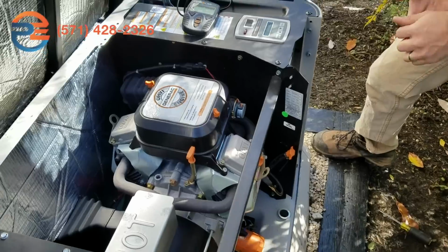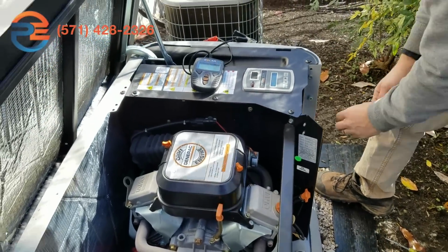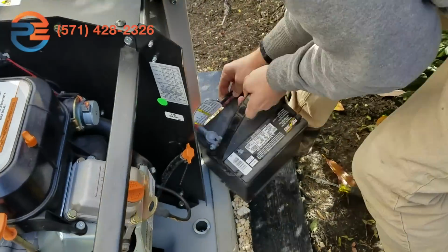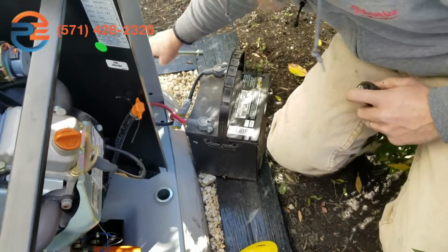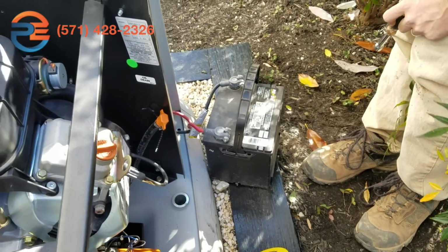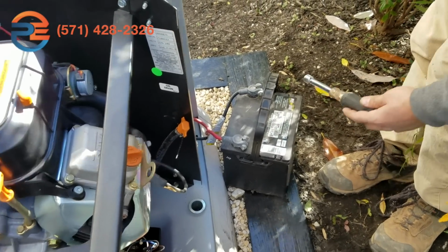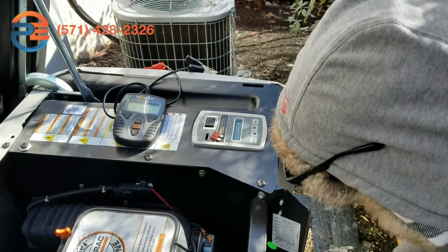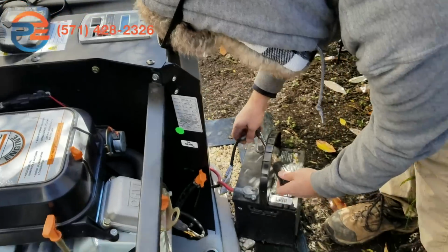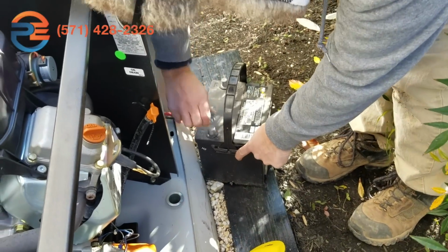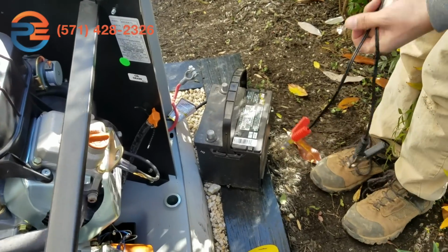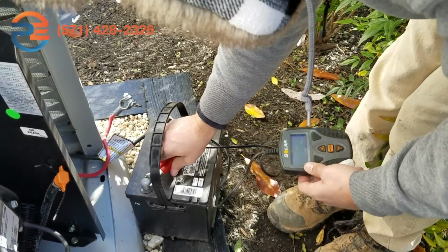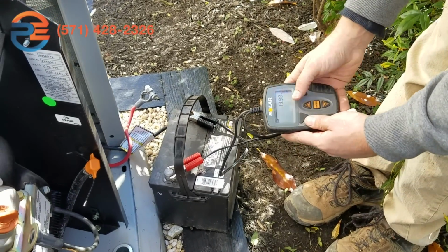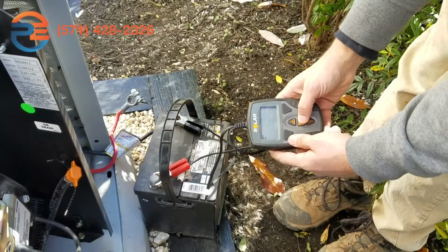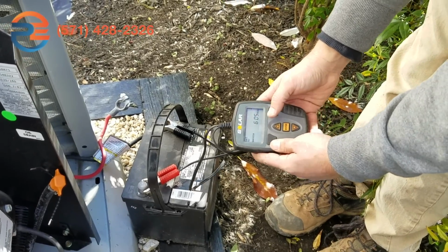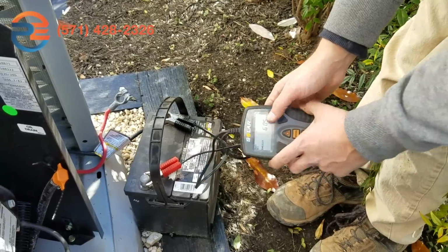We want to check and inspect our battery, so we're going to remove the battery. Using a 1/2-inch drive, we're going to disconnect the fuse from the control panel, turn the generator to off, and using a 1/2-inch drive, remove the negative battery terminal first. Then move to the positive terminal. And then with an appropriate battery tester, we're going to want to test the battery to see if it's good. Right now I'm reading 13.95 volts and 605 cold cranking amps. So this battery is good.